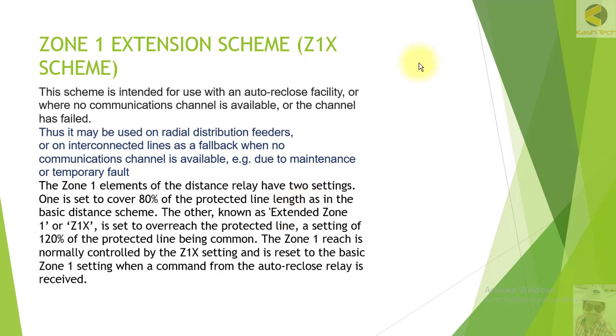The scheme we are going to discuss is Zone 1 Extension scheme, written in short form as Z1X scheme. This scheme is intended for use with an auto-reclose facility or where no communication channel is available or the channel has failed. Thus it may be used on radial distribution feeders or on interconnected lines as a fallback when no communication channel is available, for example due to maintenance or temporary fault.